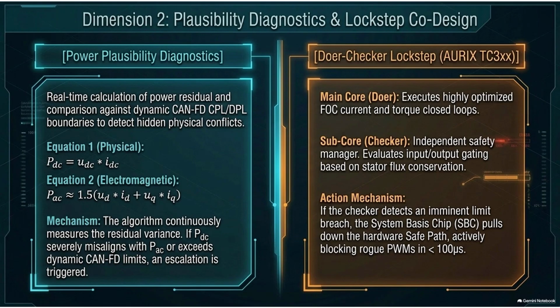Right. But running alongside it is a completely independent subcore, the checker. So does the checker just run a redundant version of the FOC algorithm to compare answers with the doer? No, actually. Because if there is a fundamental flaw in the FOC algorithm's handling of, say, deep saturation, both cores would generate the exact same flawed answer. Oh, that's true. They'd both agree on the wrong math. Exactly. So instead, the checker operates exclusively on fundamental laws of physics, like the conservation of energy and stator flux limits. Oh, that's brilliant. It passively monitors the raw sensor inputs and the doer's output commands.